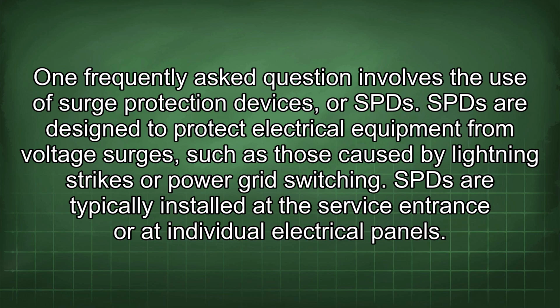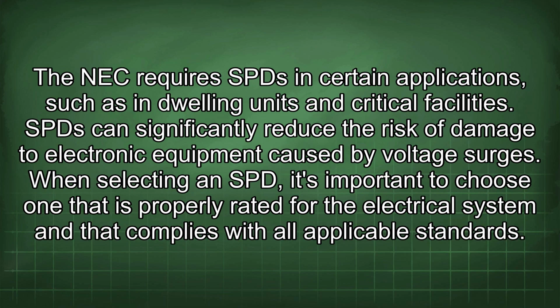One frequently asked question involves the use of surge protection devices, or SPDs. SPDs are designed to protect electrical equipment from voltage surges, such as those caused by lightning strikes or power grid switching. SPDs are typically installed at the service entrance or at individual electrical panels. The NEC requires SPDs in certain applications, such as in dwelling units and critical facilities. SPDs can significantly reduce the risk of damage to electronic equipment caused by voltage surges. When selecting an SPD, it's important to choose one that is properly rated for the electrical system and that complies with all applicable standards.